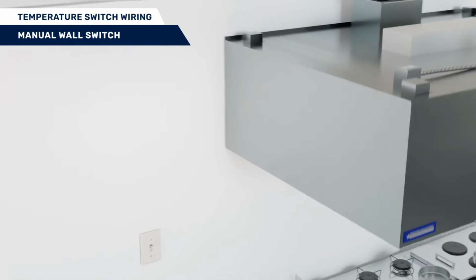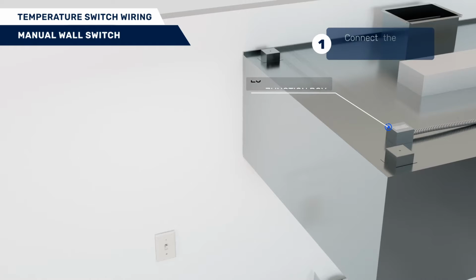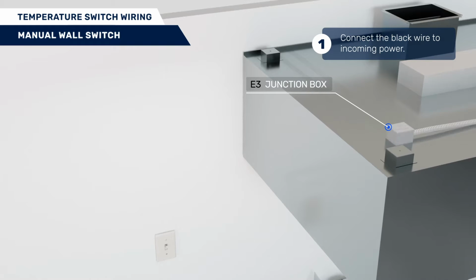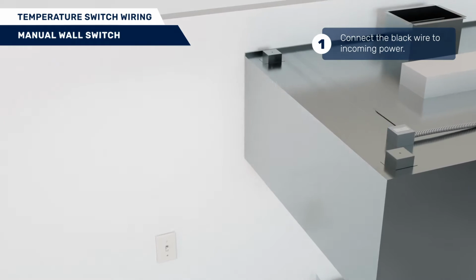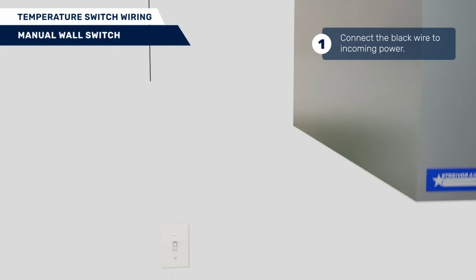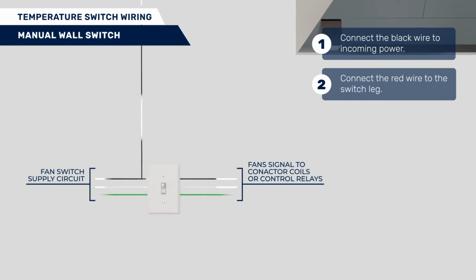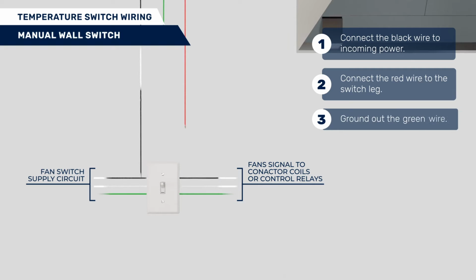If wiring the temperature switches to a manual switch, you will need to connect the black wire in the E3 junction box on the hood to the incoming power on the wall switch. Connect the red wire to the switch leg and ground out the green wire.